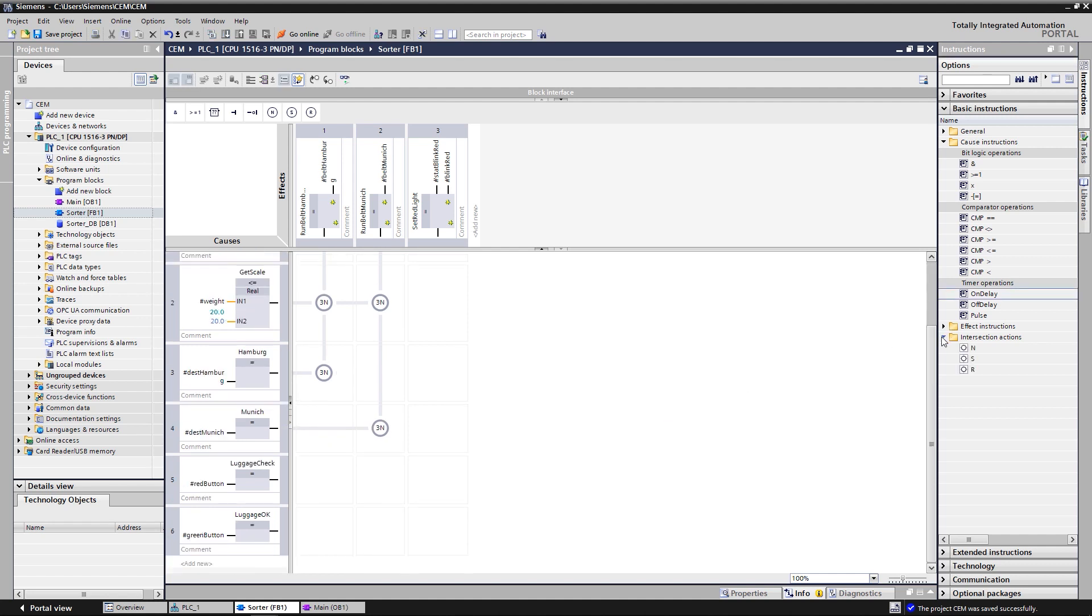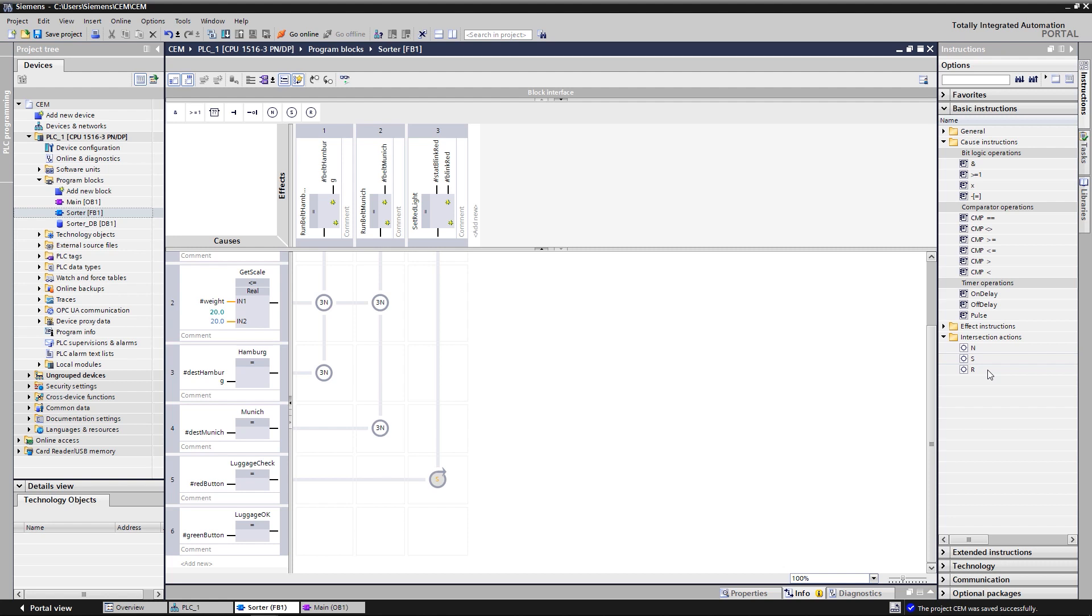At the intersection of cause 5 and effect 3, the action S for set is programmed. Its effect is that the red lamp flashes as soon as the red button is pressed. In addition, stat blink red is set. Since the action S is used here, the effect 3, set red light, stays permanently set, even if the signal red button is not present anymore.